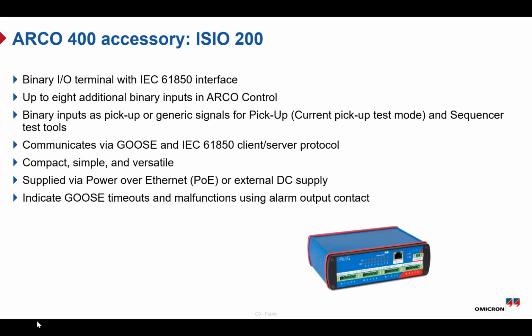Here, another accessory called ISIO 200. The ISIO 200 is a binary input and output device with IEC 61850 communication support. It allows you to add up to 8 additional binary inputs to your testing setup. These inputs can be used for different purposes, such as pickup detection or general signal monitoring during tests. The device communicates using GOOSE messages and IEC 61850 communication protocols, which make it suitable for modern digital substation and advanced applications.